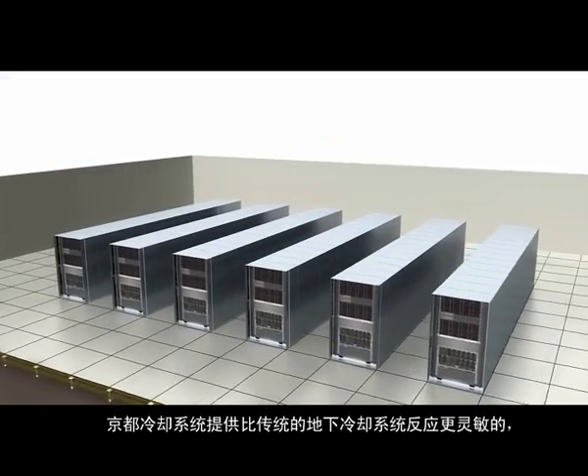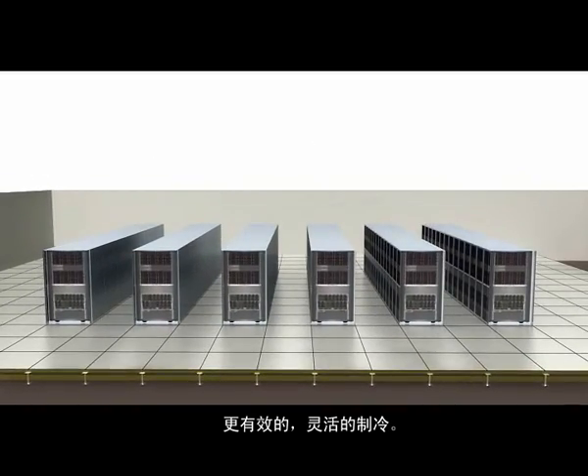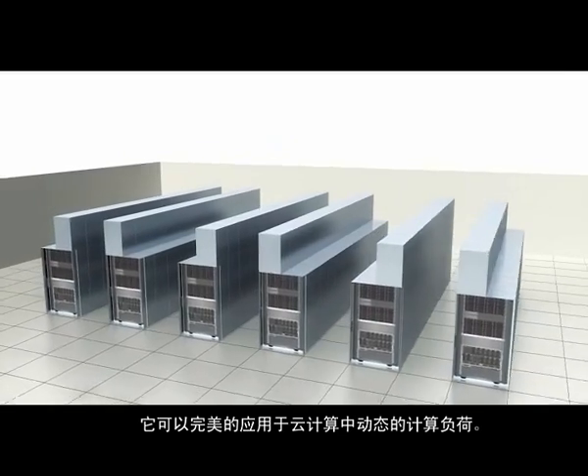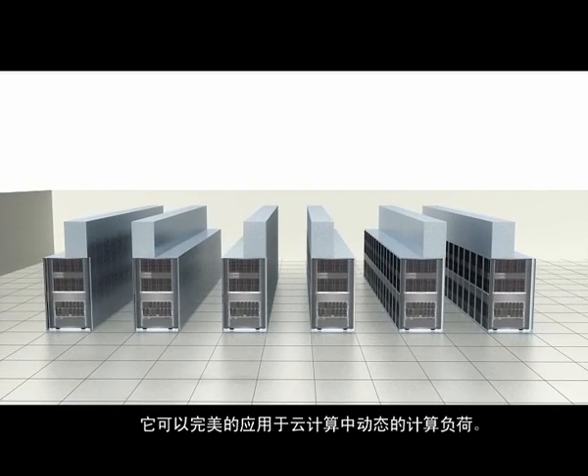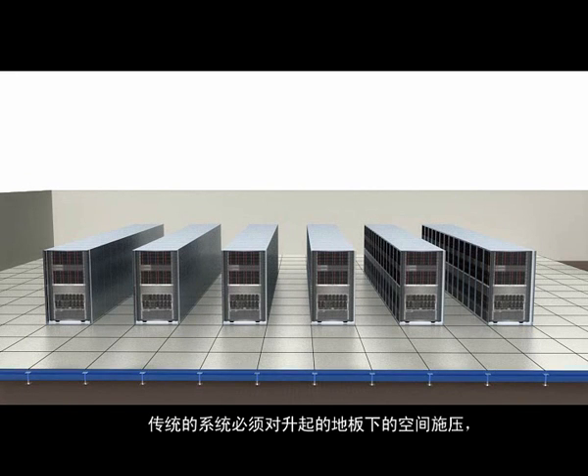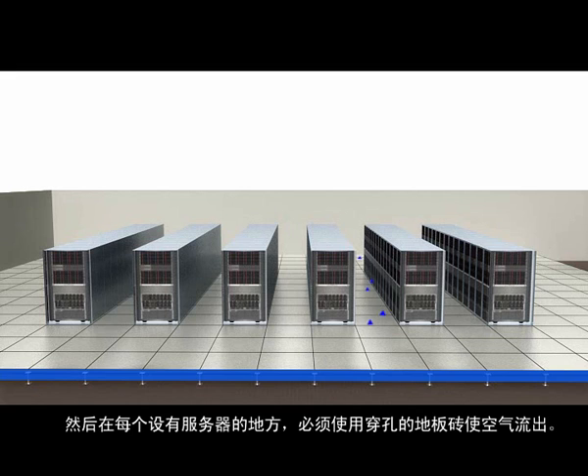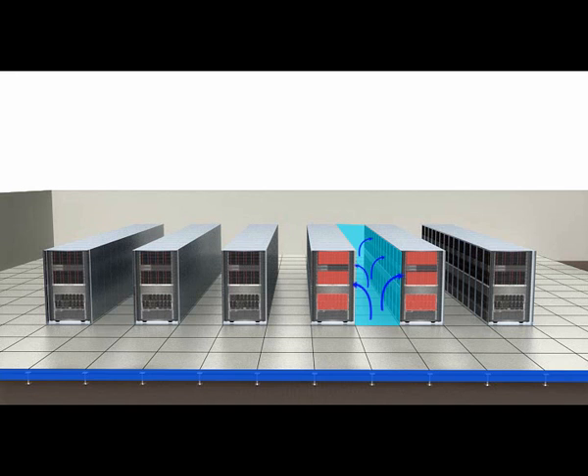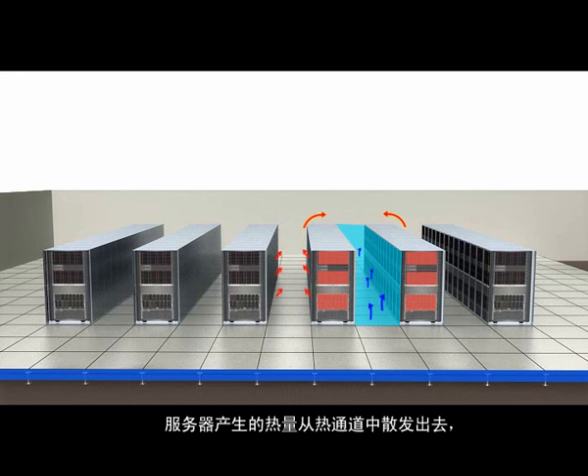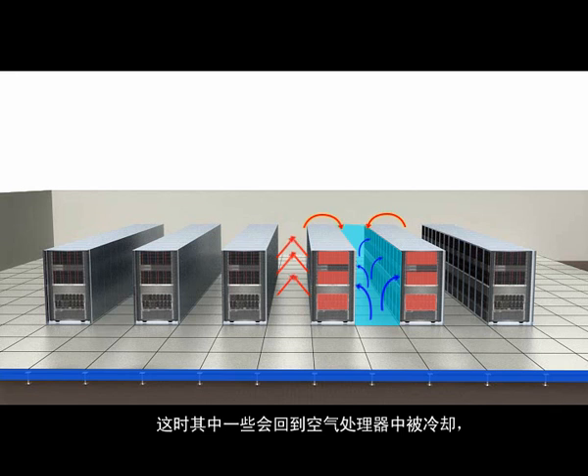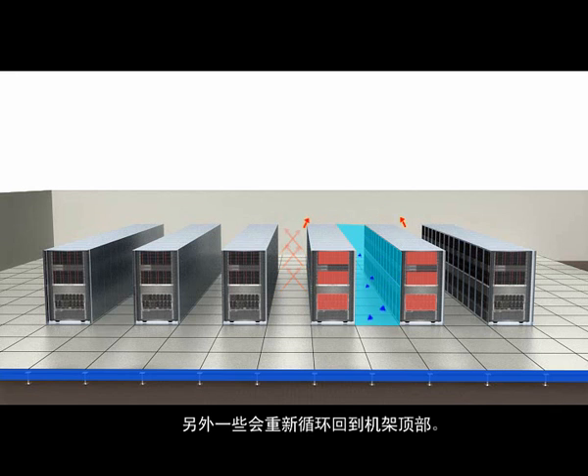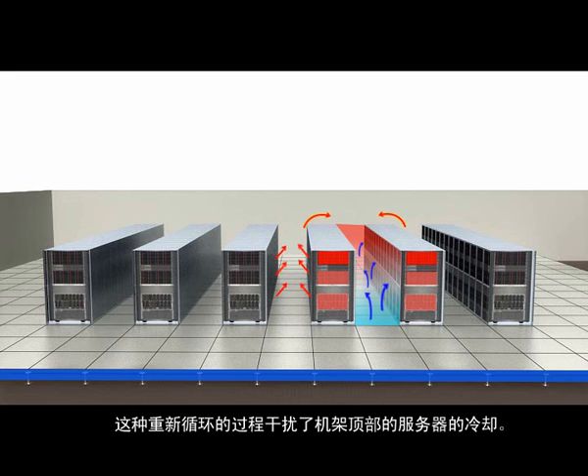KyotoCooling provides far more responsive, efficient, and flexible critical cooling than traditional underfloor systems. It is the perfect solution for the dynamic server loading of cloud computing. Traditional systems must pressurize the plenum under the raised floor to force air to every area where a server might be installed. Perforated floor tiles must then be added to release air at each location where servers are installed. Air is drawn from the cold aisle by the servers. Heat from the servers is discharged into hot aisles, where some of it returns to air handlers for cooling, but some hot air always recirculates back over the top of the racks. This recirculation interferes with the cooling of servers in the top of the racks.